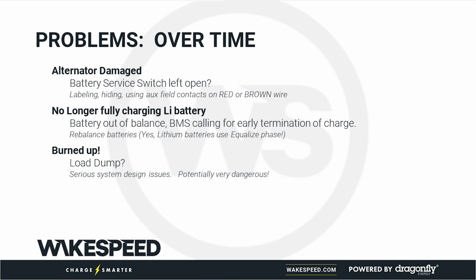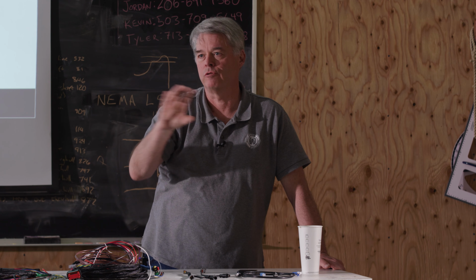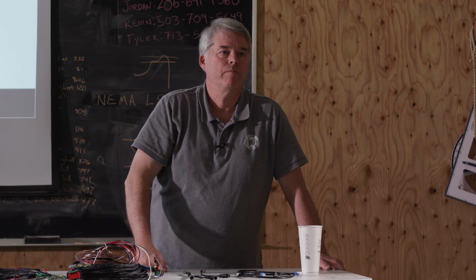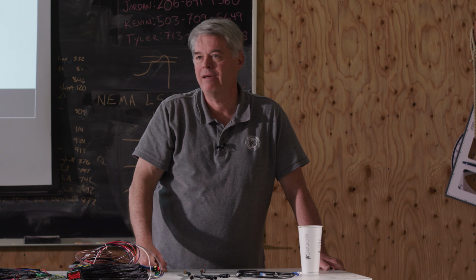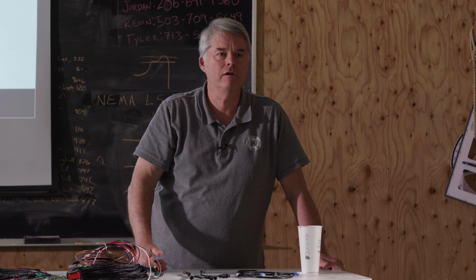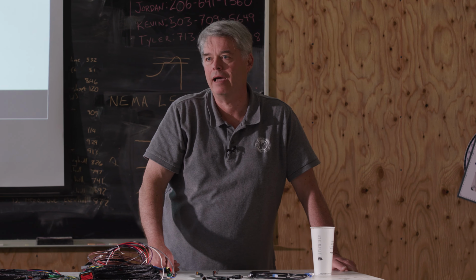Over time, yeah, this is a great one. The service switch - we have had alternator failures. We've talked a little bit about load dumps and the dangers associated with it. You get that massive voltage spike, and the avalanche diodes will suppress that. Well, what will happen over time is the avalanche diodes will eventually say, I've had enough. They're good for about 200 to 300 hits, something like that.